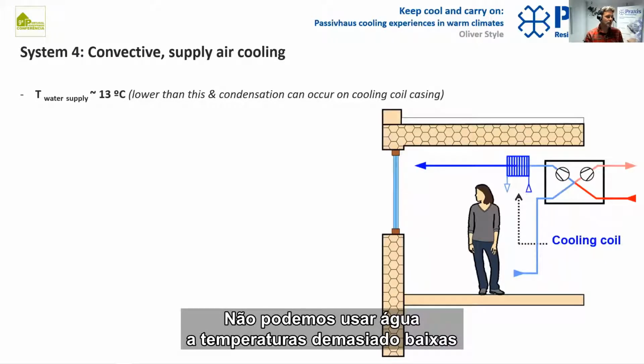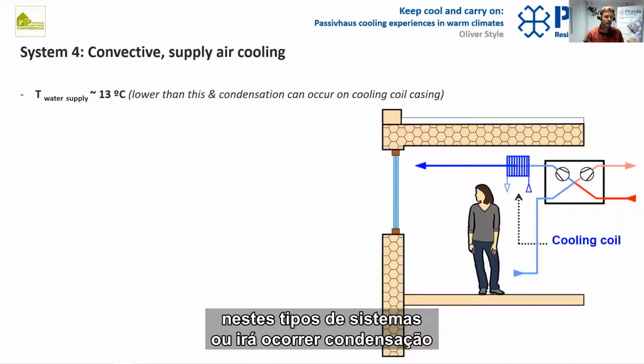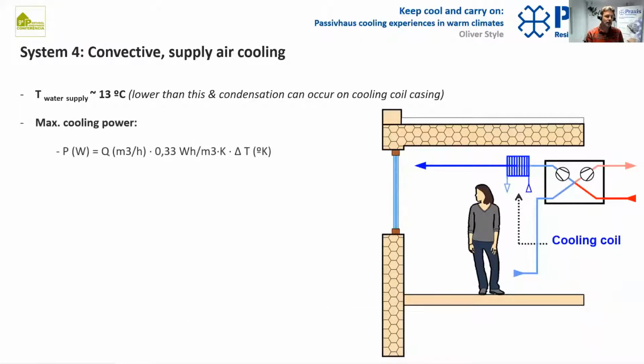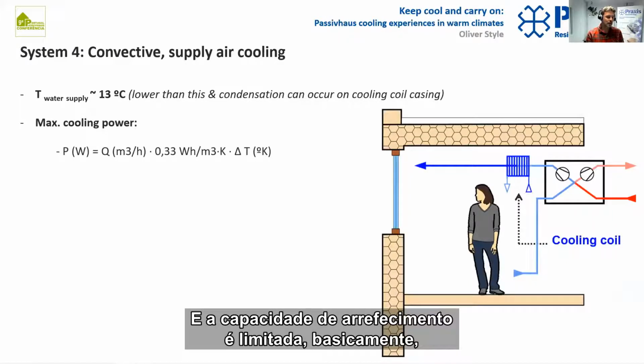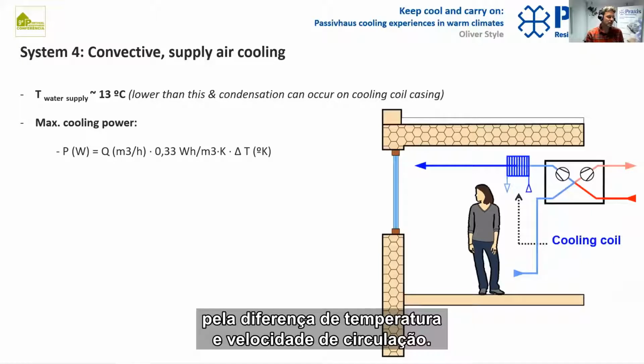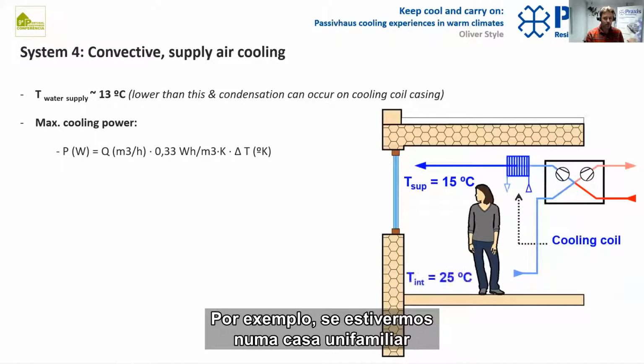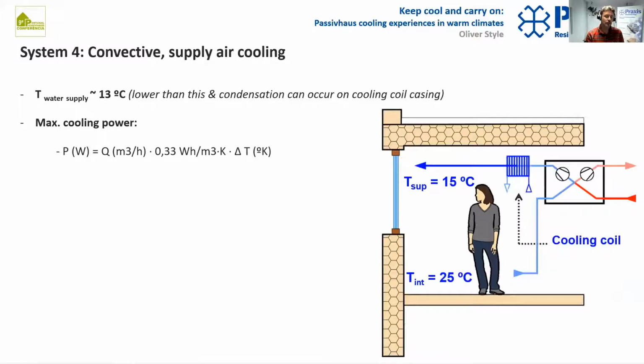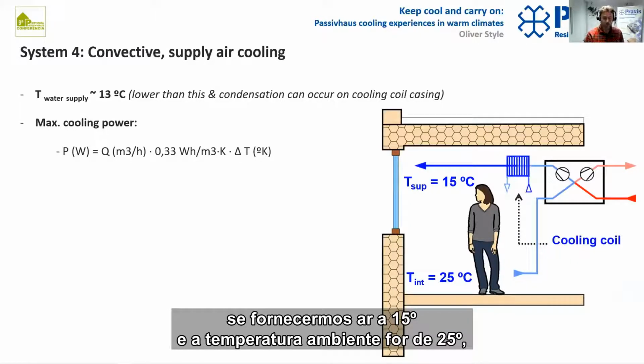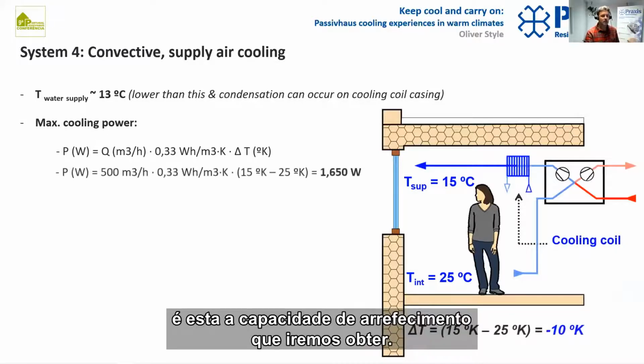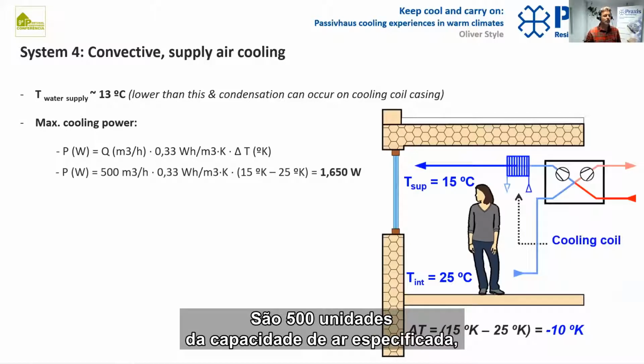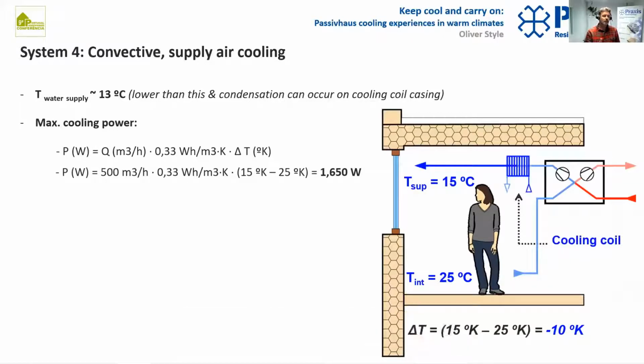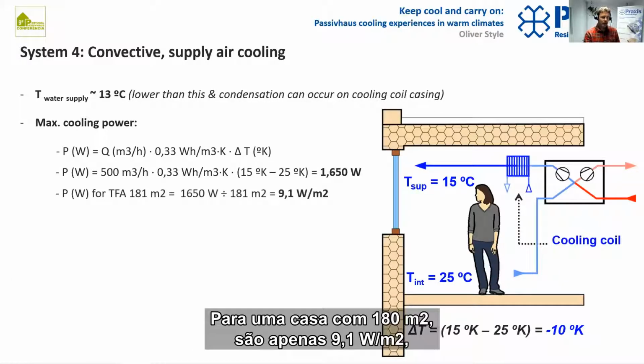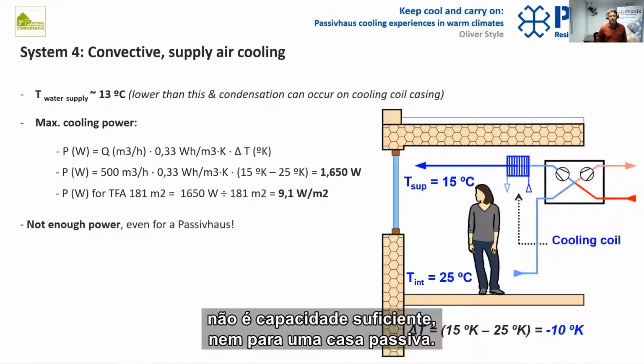We can't supply water temperature too low for these kind of systems, otherwise we found that there's condensation on the casing of the cooling coil. And the cooling power is limited by basically the temperature difference and flow rate. For example, if we are in a single family home of about 180 square meters of useful floor area, and we're supplying air at 15 degrees and ambient temperature is 25 degrees, this is the cooling power that we can get. So it's 500 by the specific heat capacity of air multiplied by the temperature difference. So that's about 1.7 kilowatts. For a house of 180 square meters, that's only about 9.1 watts per square meter. So that's not really enough power, even for a passive house.